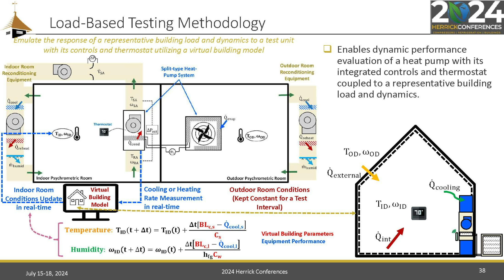And that gets programmed into the equipment room controls, the test room controls. The outdoor room is held constant at one condition, and the load that you put on the indoor unit, on the indoor room, varies depending on how cold or how hot it is outside. So when you're testing really cold outdoor temperatures and heating, you give it a bigger load. And when you're testing mild temperatures, you give it a smaller load. That make sense?